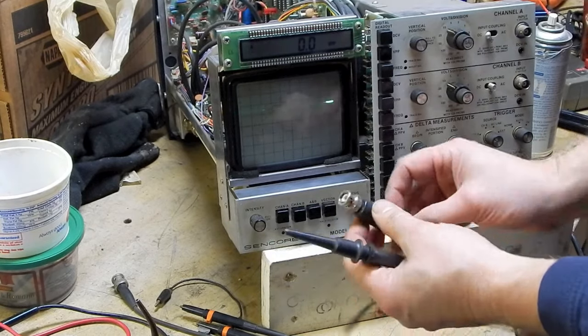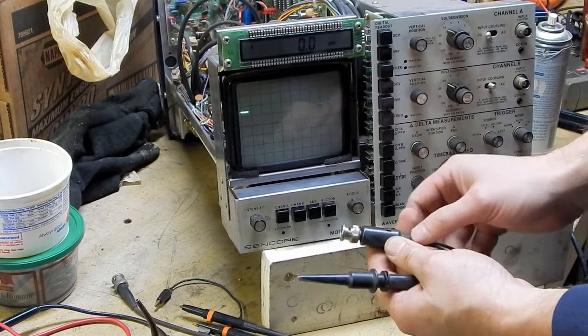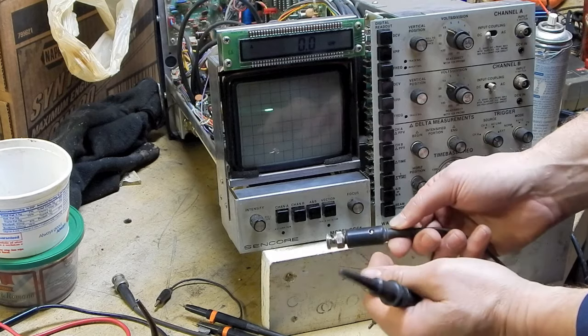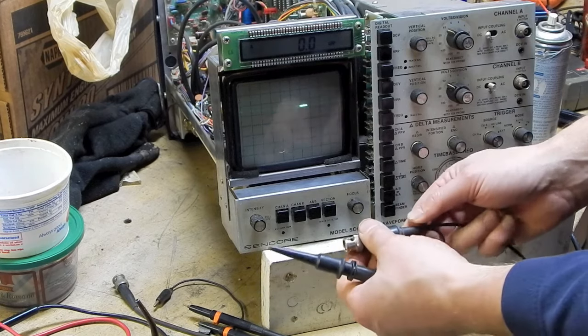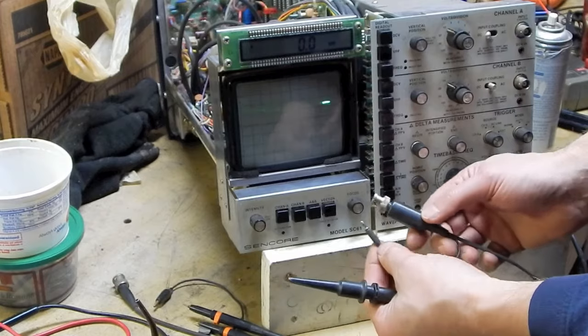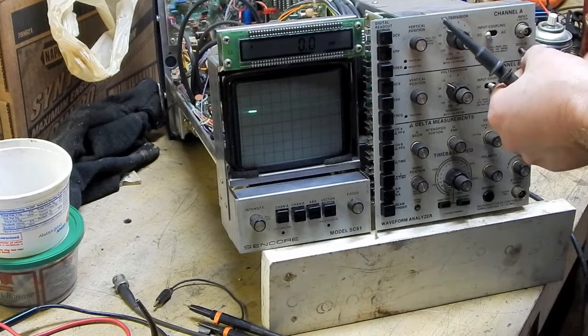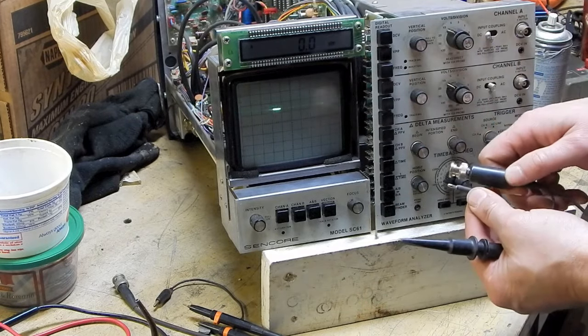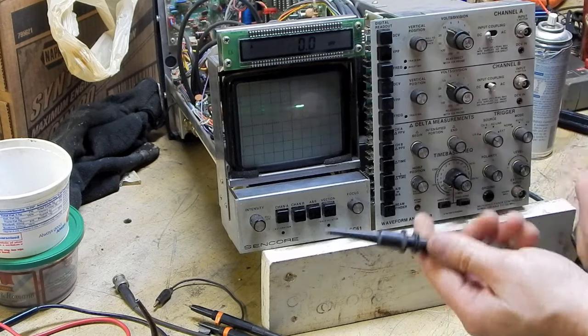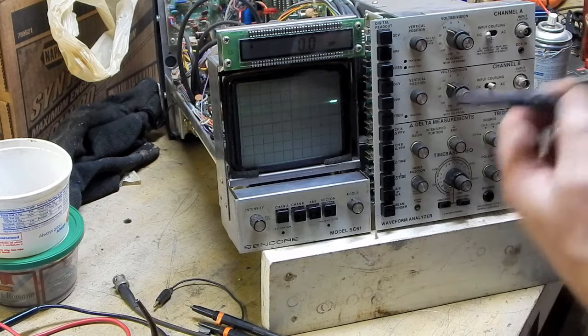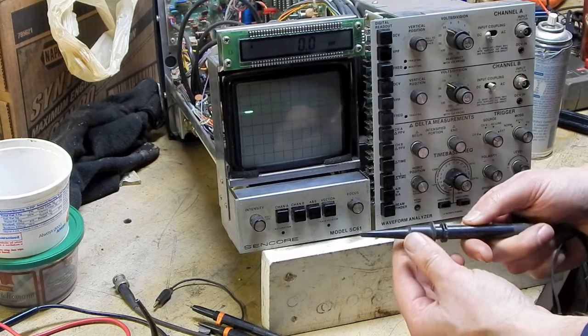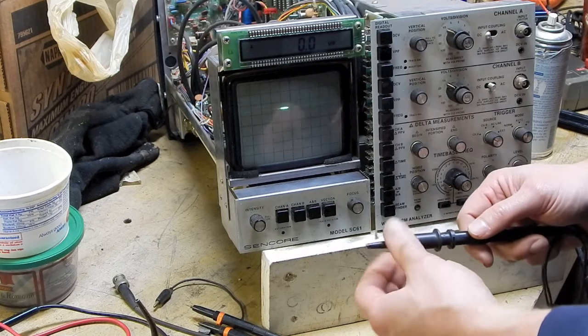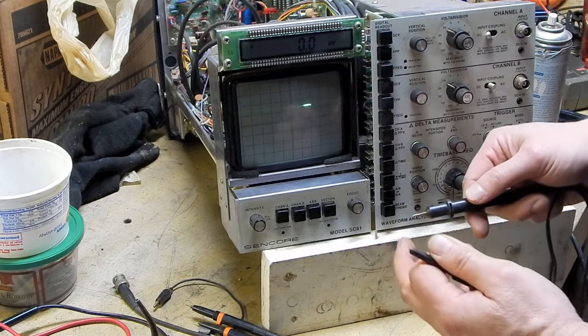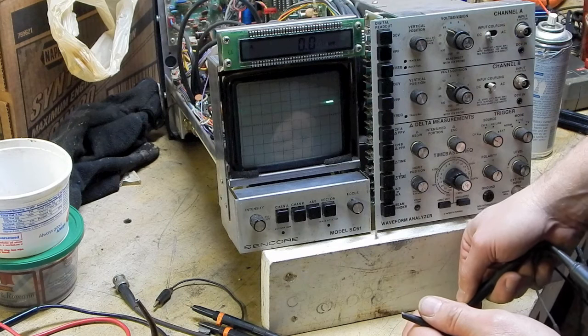So what you've got is the typical BNC connection, and then there's a compensation circuit inside here, and there's a little set screw in there for that, and then there's this extra wire here. This is for your DC input right there, okay? And then on the other end you've got the probe, and it came with different attachments.